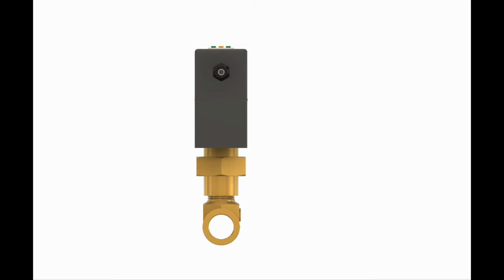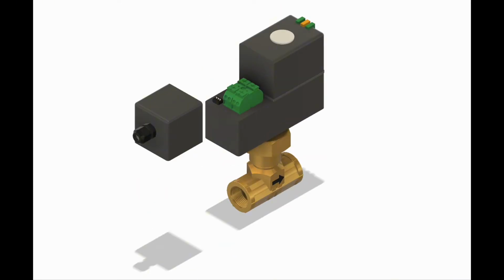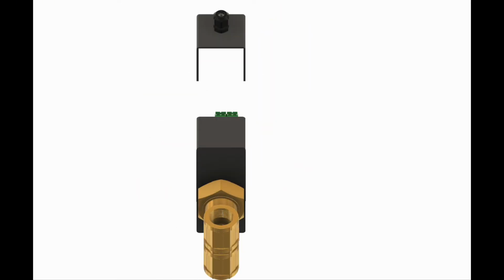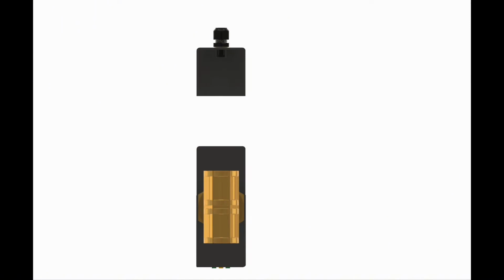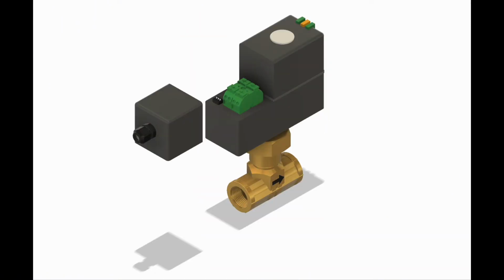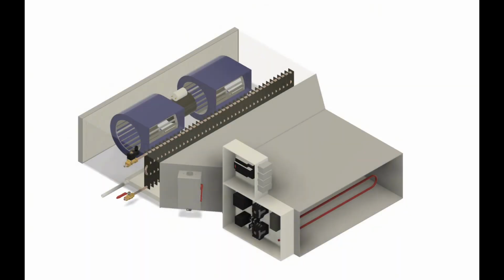So these would go in line on the chilled water line on your fan coil units, like in our commercial office building, providing chilled water to all the fan coil units. So when you call for cooling, the controller would send 24 volts to that PIC valve, and the controller sits inside this control box on the side of each fan coil unit in the commercial office space, up in the drop ceiling. And again, all this is controlled by your BAS.